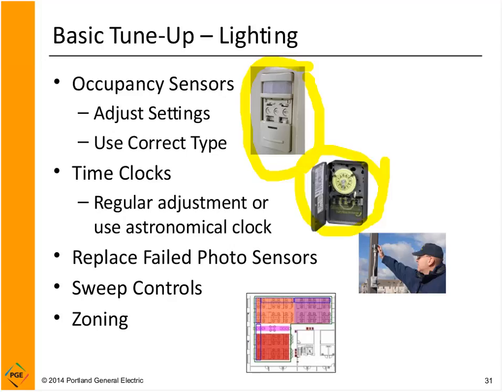Down on the list is time clocks, and this type of technology is something you're going to see in an older building. Just because it's old technology doesn't mean it won't work for you, it just means you need to pay a little more attention to it. This time clock revolves around a mechanism with pins in it that determine when to turn on and off a piece of equipment. This isn't just for lighting, it could be for a recirculation pump on your hot water system or something of that nature too. So whenever you have a time clock, periodically check it, make sure the pins didn't fall out, and make sure they're still set at the time you want to turn the equipment on or off.